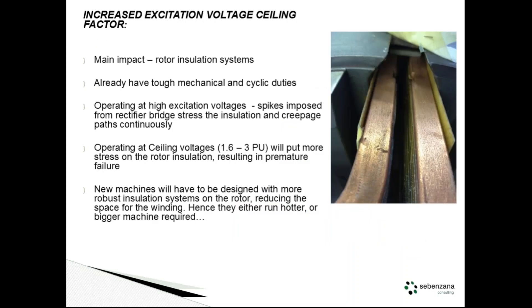Increasing the excitation voltage ceiling factor: currently we're looking at 1.6 per unit as the maximum; now they're saying push that to 3 per unit. Looking inside a rotor, we're looking at the slot liners and the turn insulation between turns. These already have a tough time from mechanical cyclic stresses — every time you run the machine up and down you're putting stress on the insulation. If you have static excitation systems, you're already getting high frequency pulses from the rectified bridges stressing that insulation. Now wanting to apply even higher voltage adds more stress and premature failure. New machines will need more robust insulation systems — more insulation means less copper, so they'll run hotter, or you build a bigger machine. In both cases, expense.